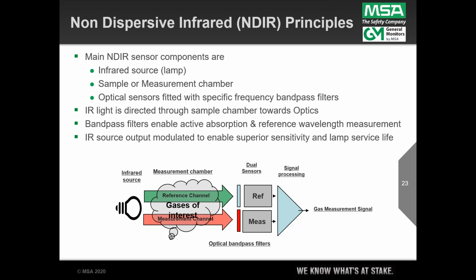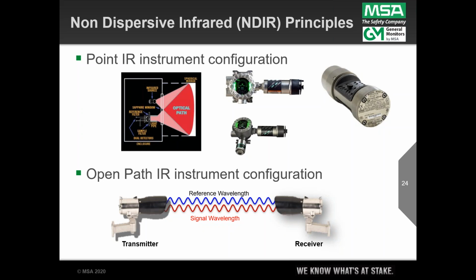Now, the strength here is, again, where the cat bead sensor, which is destructive, may last 3 to 5 years, maybe longer, you can expect this type of technology, because it's not having to burn anything or create heat, as long as you're not vibrating it to death, to last 10 years and beyond. They can be packaged in 2 different ways. They can be packaged in a point infrared instrument, and I've got some examples in the upper right-hand corner there. These are point detectors that are placed using the same thought process and evaluation principles as cat bead or toxic point detectors. But then you've also got this open path infrared instrument configuration shown across the bottom, where essentially our engineers have taken the lamp out of the point infrared instrument and put it into a module called the transmitter, and stepped it up.